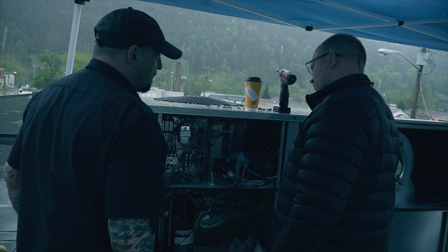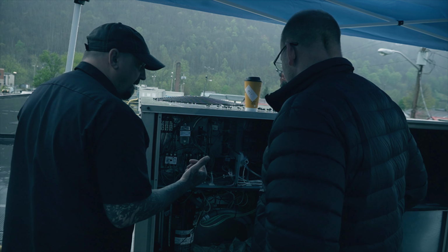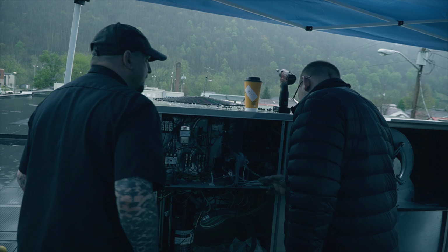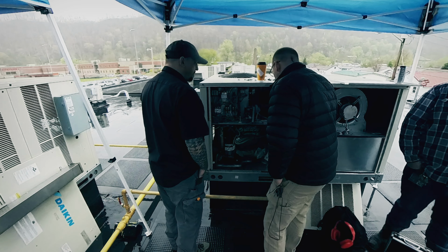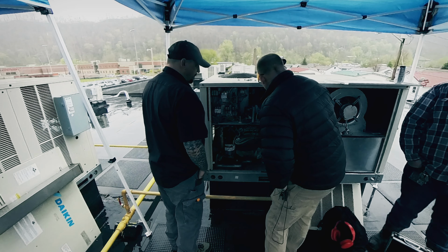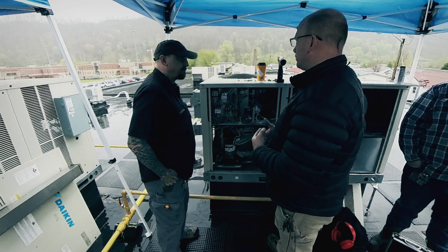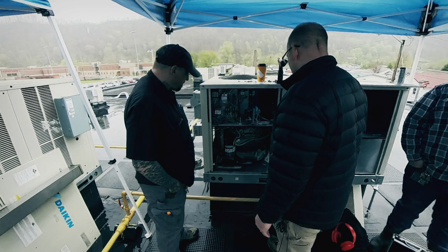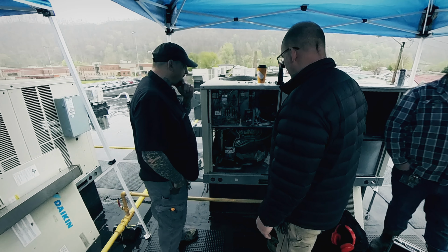That's just your filter switch, your vacuum switch. On one unit I was on the other day, the vacuum switch caused my fan not to work because it was blocked and clogged up. I don't think this is set up like that. The way I see this, it just goes back to here, so it's pretty much just a reader. Okay, makes sense. So this one here is totally set up differently than the rest I've seen.